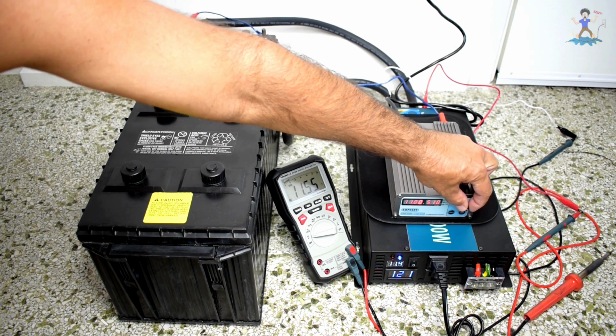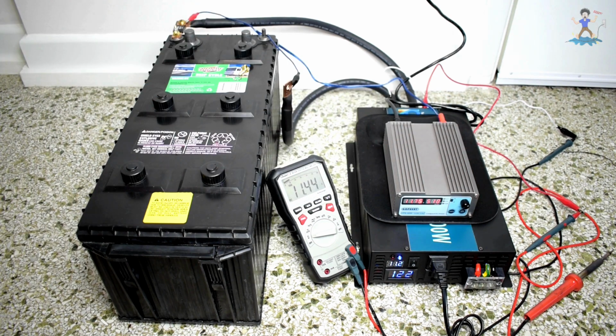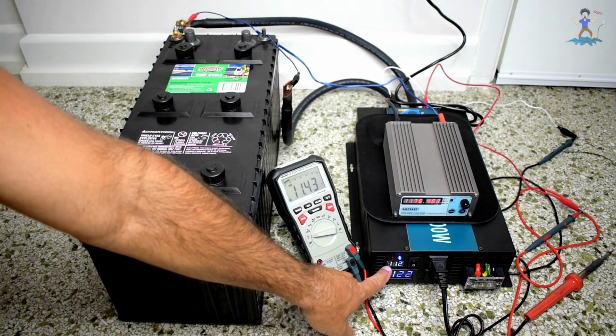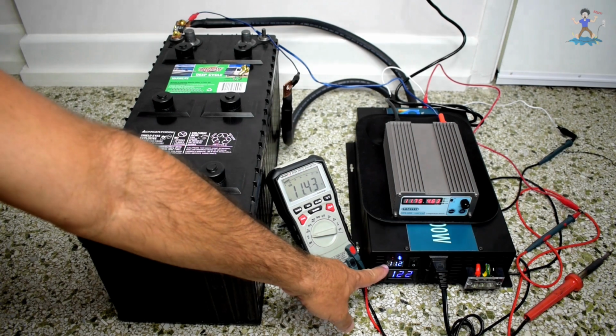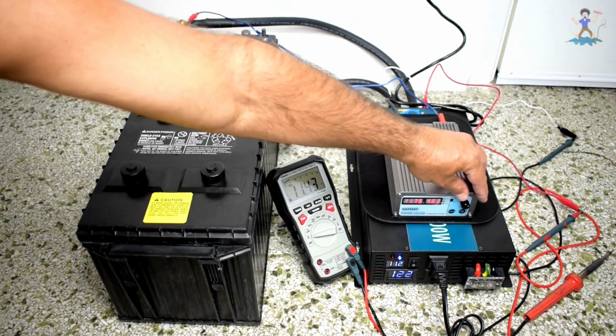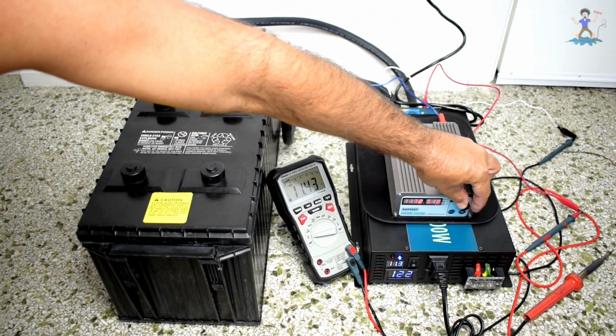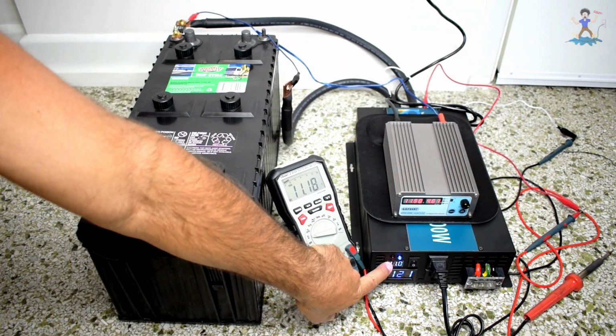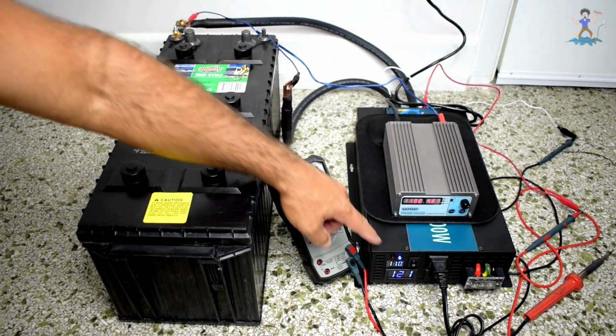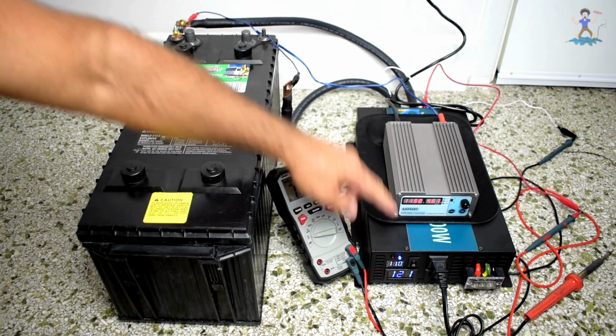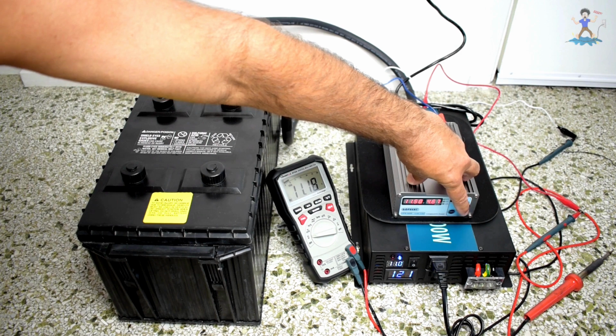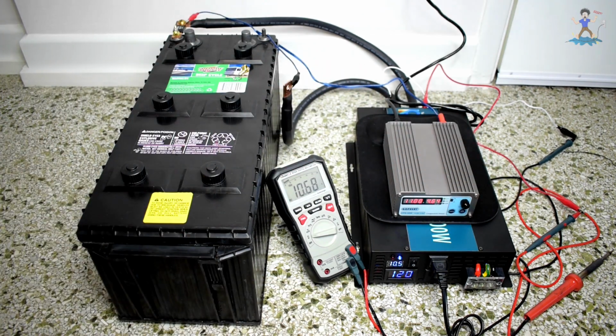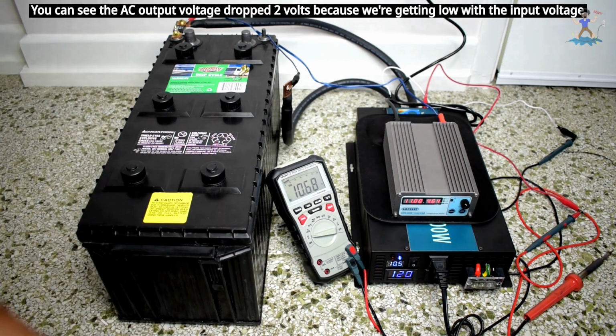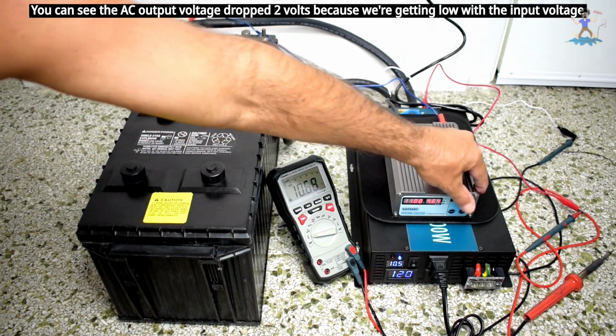Let's bring it down to 11.75... 11.43, 11.2, and 3 flashing. Let's bring it down to 11.5. This is now at 11, still supplying power. They say 10 volts is where this is going to trigger. Let's bring this down to 11, then 10.5. Output still 120. 10.6.